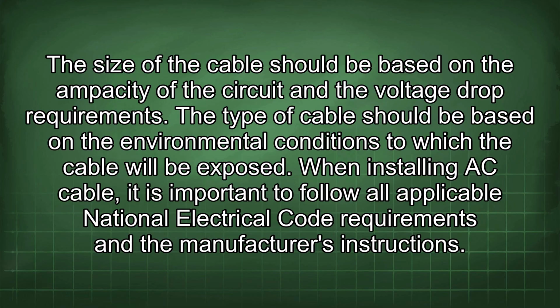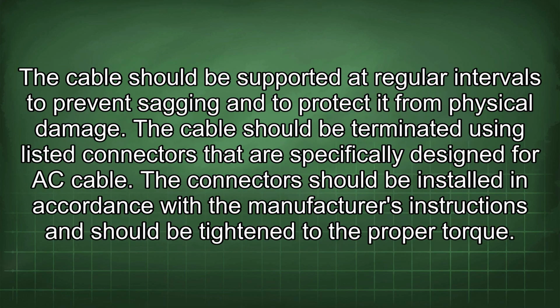When installing AC cable, it is important to follow all applicable National Electrical Code requirements and the manufacturer's instructions. The cable should be supported at regular intervals to prevent sagging and to protect it from physical damage. The cable should be terminated using listed connectors that are specifically designed for AC cable.